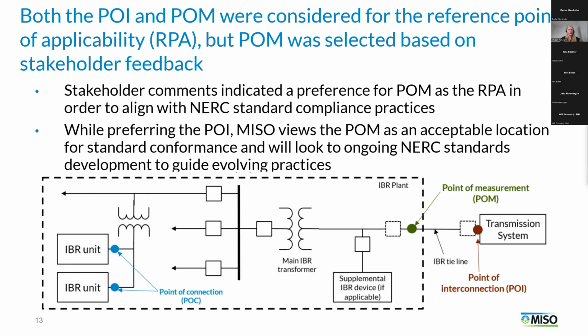MISO considered both the point of measurement and the point of interconnection as possible locations for the RPA. We proposed the POI initially because we saw it as the best reliability supporting solution from the transmission system perspective to include that IBR tie line there. But we received some substantial stakeholder feedback pushing for the POM instead, just because it aligns with current standard compliance practices. For example, PRC 24 requirements apply at the POM. So we agreed with the points that stakeholders made and saw POM as an acceptable RPA. That's also the default in 2800. And so we moved forward with that.